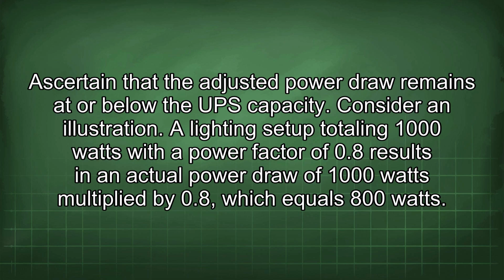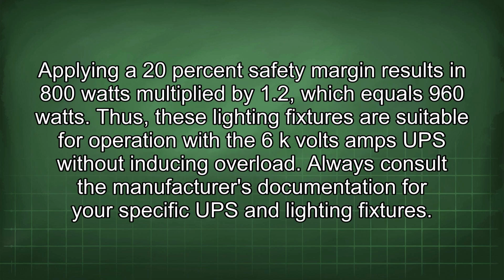Consider an illustration. A lighting setup totaling 1000 watts with a power factor of 0.8 results in an actual power draw of 1000 watts multiplied by 0.8, which equals 800 watts. Applying a 20% safety margin results in 800 watts multiplied by 1.2, which equals 960 watts. Thus, these lighting fixtures are suitable for operation with a 6 kVA UPS without inducing overload.